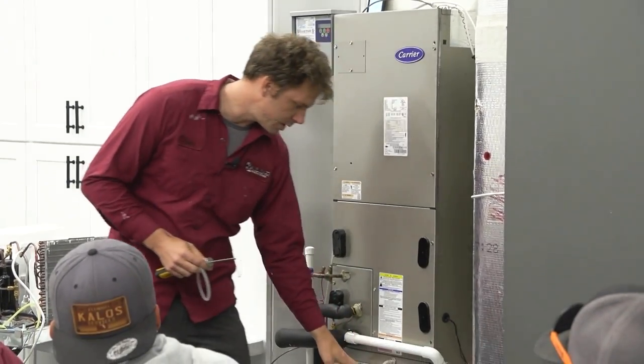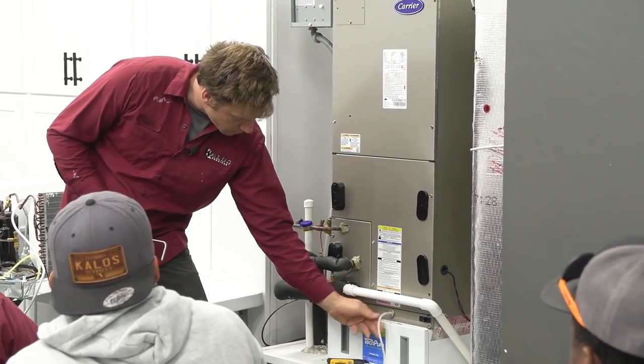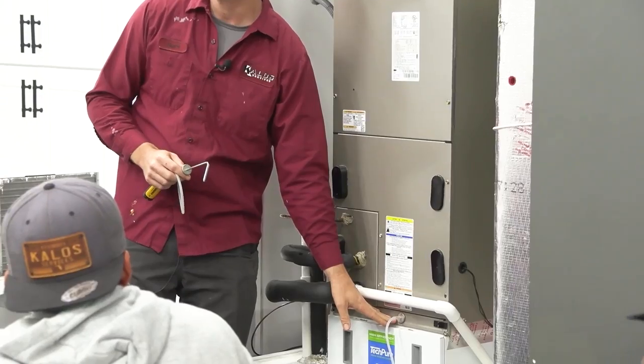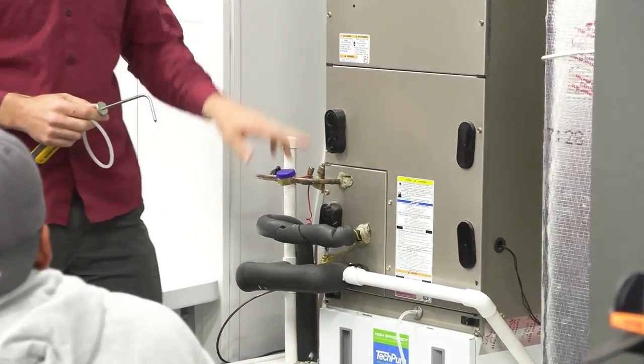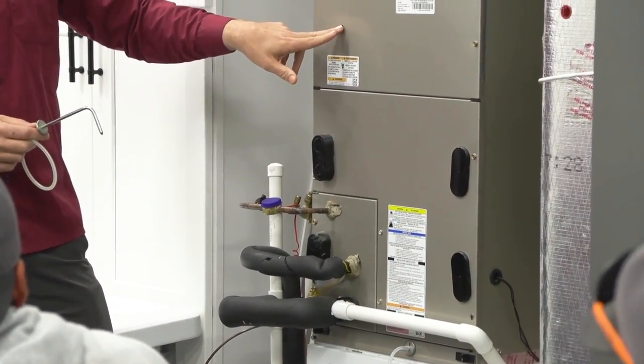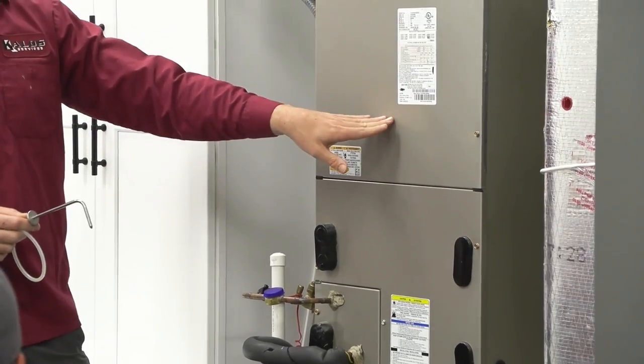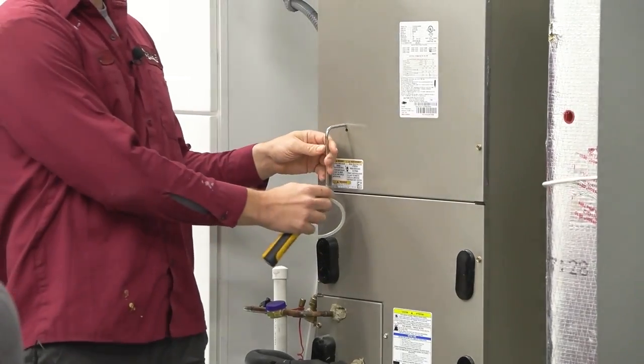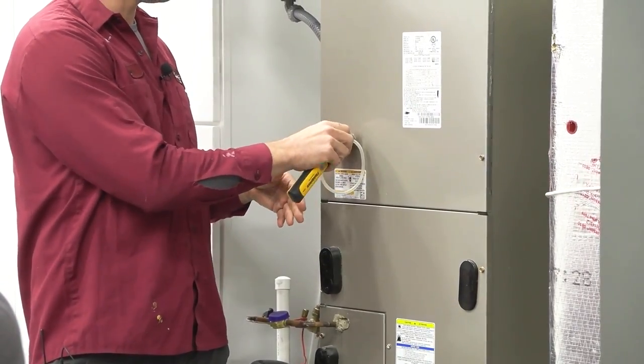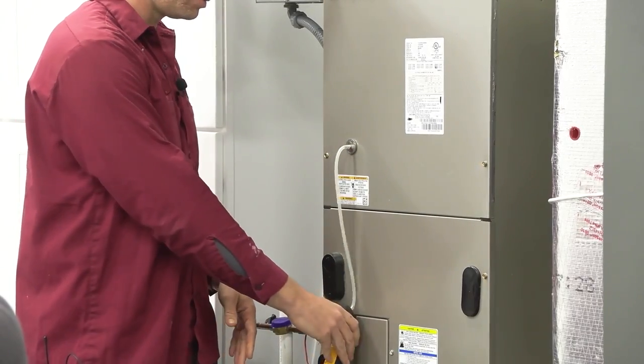Sometimes the coils are this thick, so you don't really know if it's impacted internally and we've got algae growing. On a coil, you can do a pressure drop across your coil. I'll leave this one in the return. This one is above the filter, right below the coil. Then you drill a hole in your compartment where the blower is above the coil and you put your supply one in there. You're just looking for a difference between the two.